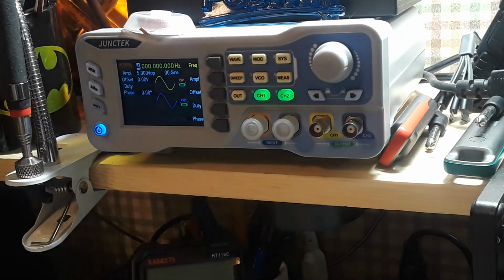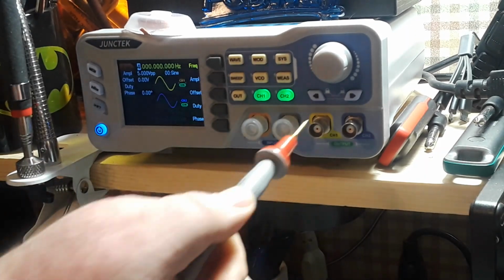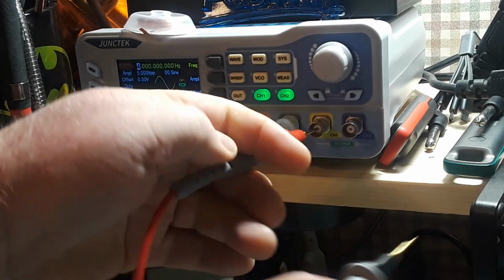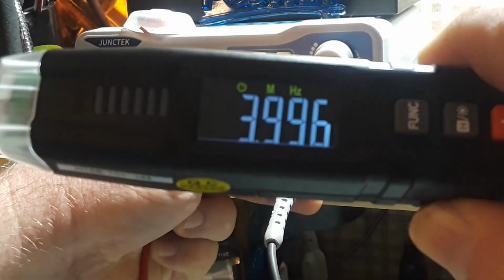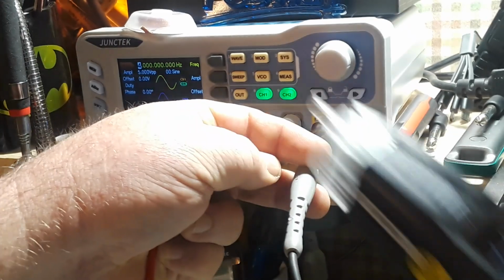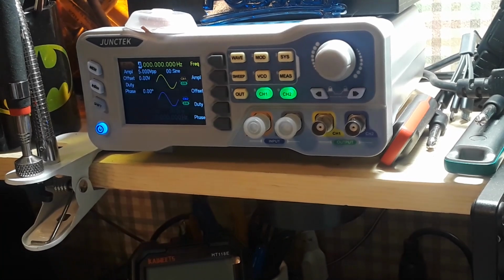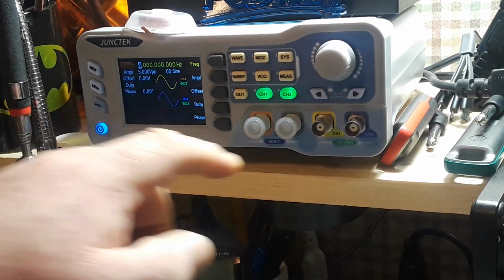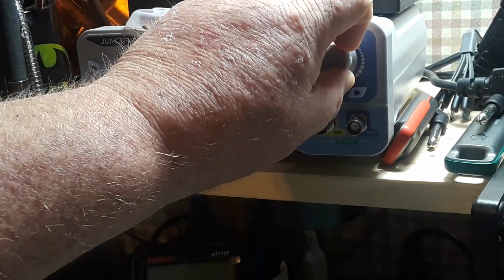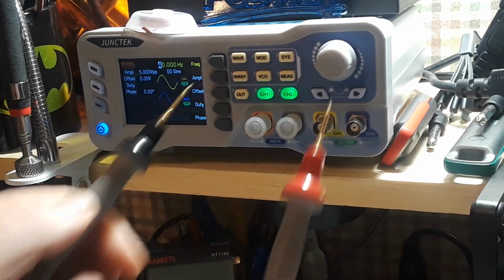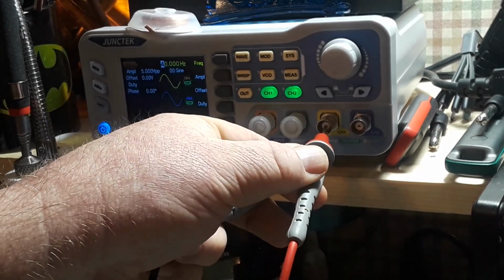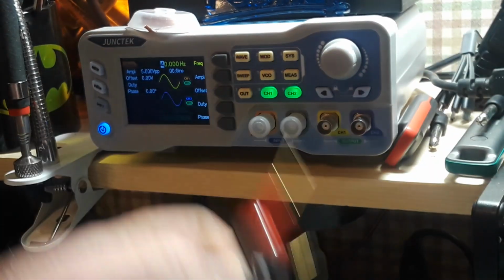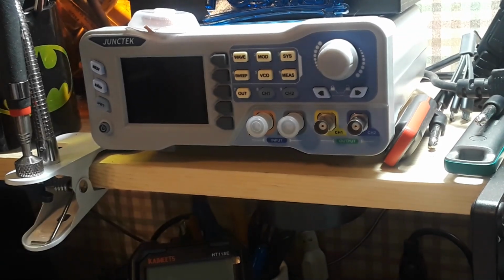So there is a 4 megahertz sine wave coming out of channel 1. And we get 3.996 megahertz. And what was the lower limit? 40 hertz. There's 40 hertz. And we're getting 39.95. So that's great.